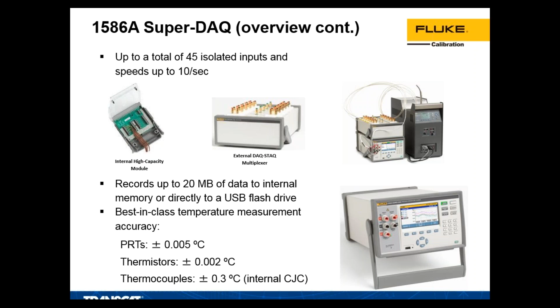PRT is quite accurate, up to plus or minus 0.005 degrees Celsius, and thermistors to 0.002. It's a very useful tool, and it can control all of the Fluke temperature sources, such as the 9118A thermocouple furnace, Fluke baths, or a dry well—you name it, it can control it. So it's a pretty powerful tool in that regard.